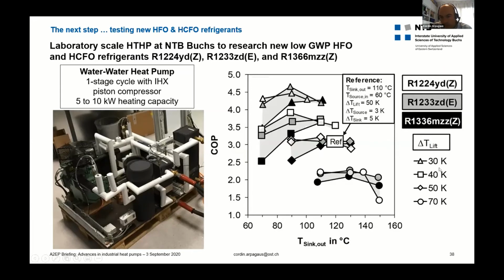Let's look at the 50 Kelvin lift—these curves here we use as a reference point. At this point, the heat source is 60 degrees, which could be available waste heat from industry, lifted up to 110 degrees, giving a 50 Kelvin lift. So we reached a COP of around 3.2 with the internal heat exchanger design.